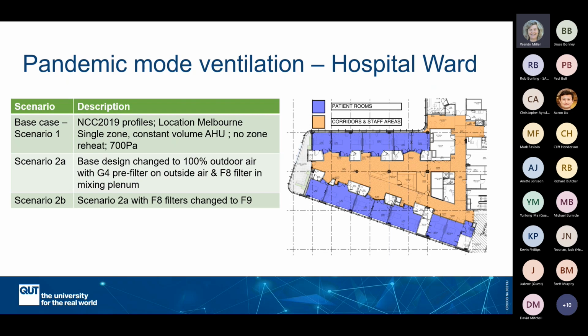And then it was compared to 2 scenarios. So scenario 2A is that same design and ventilation system, but changed to 100% outdoor air, with a pre-filter on the outside air and an F8 filter in the mixing plenum. And then scenario 2B is the same as scenario 2A, only the F8 filters have been changed to F9 filters. So what was the impact of that?